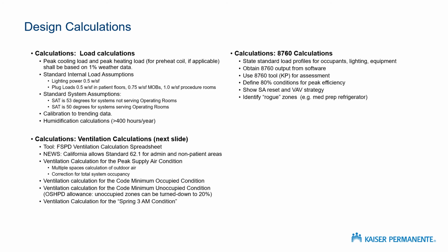Then of course, design calculations. We get it, right? We expect calculations for air handling projects. If you have some feedback from the facility, it is probably fair to assume that the peak load calculations done by the previous engineer aren't undersized. That's probably fair, right? So generally the CFM that you find in the room is okay for peak loads.